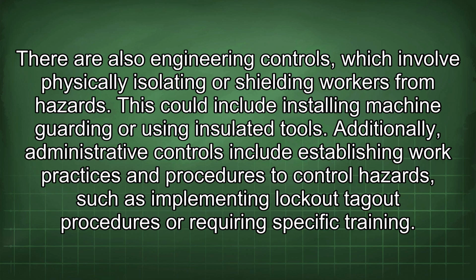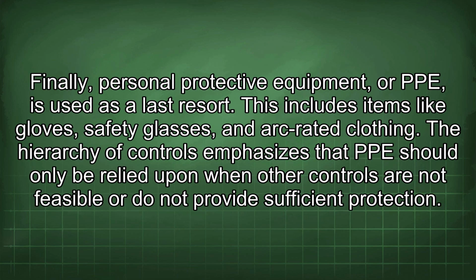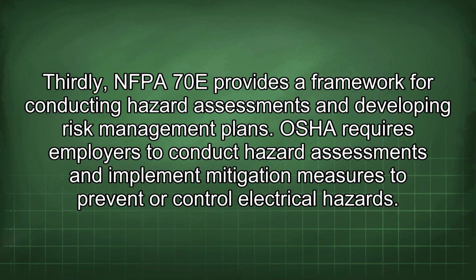Additionally, administrative controls include establishing work practices and procedures to control hazards, such as implementing lockout-tagout procedures or requiring specific training. Finally, personal protective equipment, or PPE, is used as a last resort. This includes items like gloves, safety glasses, and arc-rated clothing. The hierarchy of controls emphasizes that PPE should only be relied upon when other controls are not feasible or do not provide sufficient protection.